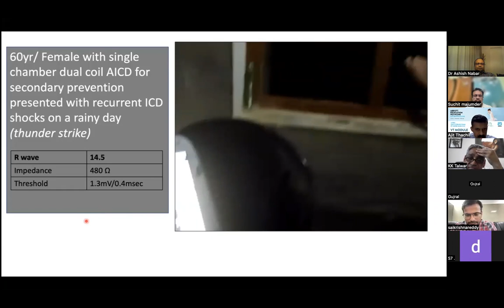And this is another case, where a 60-year-old female had an implanted dual coil AICD for secondary prevention. She presented to us with recurrent ICD shocks. This was on a rainy day. She actually thought it was a thunder strike and presented to us the next day. On evaluation, her lead parameters were normal. Then we had a suspicion, and the EGM, which is not displayed here, had shown it as EMI, but the device was inappropriately giving a shock.